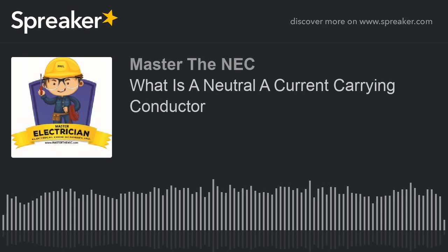And then, of course, if we have the certain number of current carrying conductors, and again, we're going to talk about what constitutes a certain number, then we're going to have to do what's called an adjustment. Together, for people to keep it from getting confused, I guess we use the term derating, and it really doesn't matter because I hear all the time, and I'm guilty of it. I'll talk about adjustments when I'm dealing with temperature, which is supposed to be a correction, and when I'm dealing with the number of conductors, I'll sometimes say correction, which is actually an adjustment. I think at the end of the day, we know what we mean.